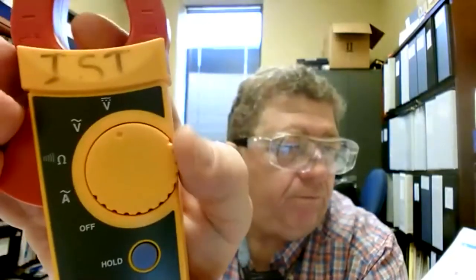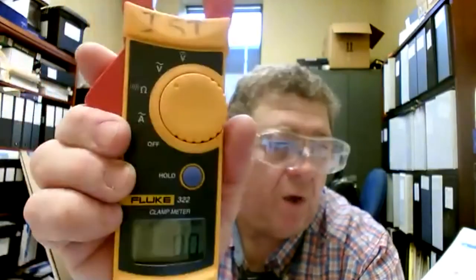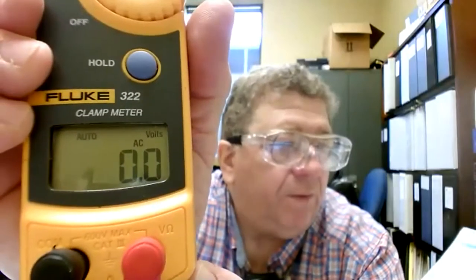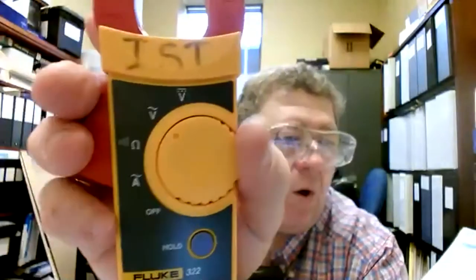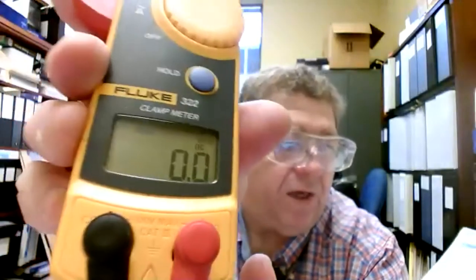So if you're not sure what the voltage is in a circuit, the safest thing to do is check it on both settings on this meter. Go to the AC setting, and you see it says AC on the screen, and then test it. If it says zero, then go up to the DC setting, and you see it says DC there, and you check the same circuit and see if it says zero. So if you're just not sure if it's AC or DC, check it on both on a meter like this before you proceed to put your hands on that circuit. Okay?